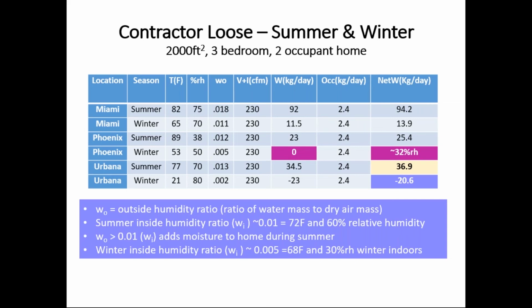So, 0.005 is roughly about a 30% relative humidity indoors at 68 degrees Fahrenheit. And so for Phoenix, if you did not do anything moisture management wise, so zero humidification, dehumidification, and just let it float, it would be about 32% relative humidity. And then Urbana is humid in the summer, more humid for sure than Phoenix. And then in the winter, because of the poor sealing, if one were to keep it at about 30% relative humidity indoors, you'd be adding about 20 liters of water per day.